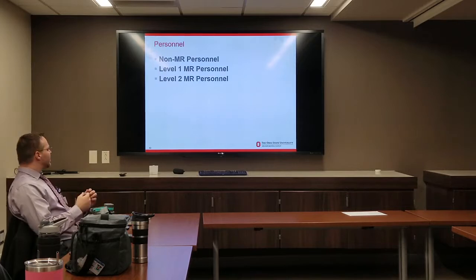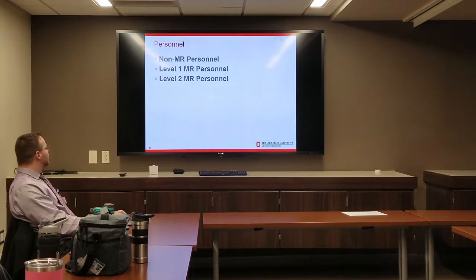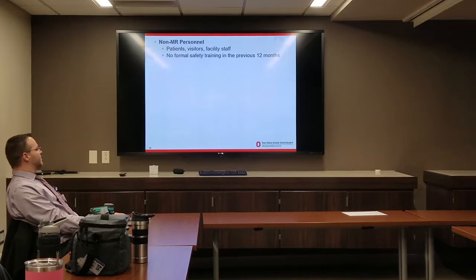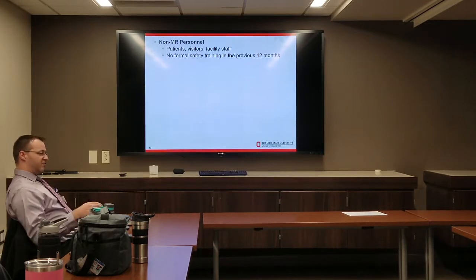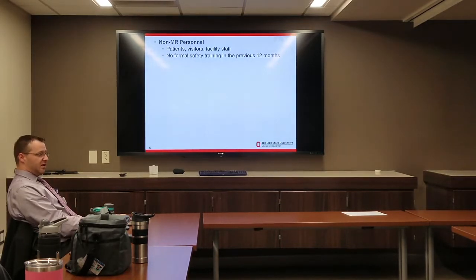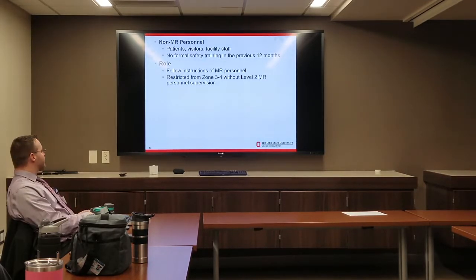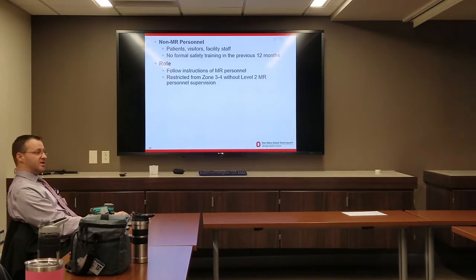For personnel, there are three categories: non-MR personnel, Level 1, and Level 2. Non-MR personnel include patients, visitors, and facility staff — possibly some nursing staff. Basically, if they have not had formal safety training in the past year, they are considered non-MR personnel. Their role is to follow the instructions of MR personnel when in that environment. They are restricted from Zones 3 and 4 unless there is Level 2 supervision present.